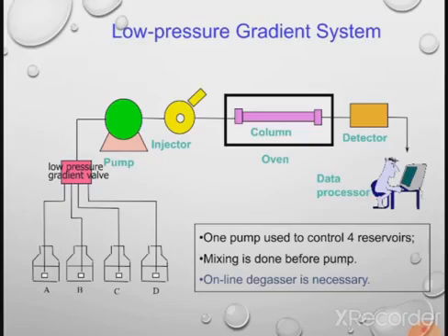The mixing is done before the pump, so it is called the low pressure gradient pump.